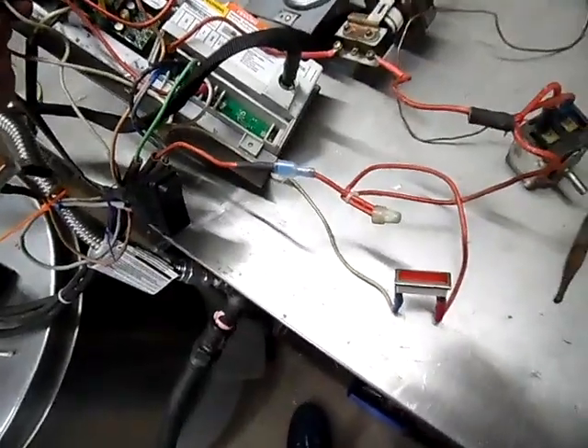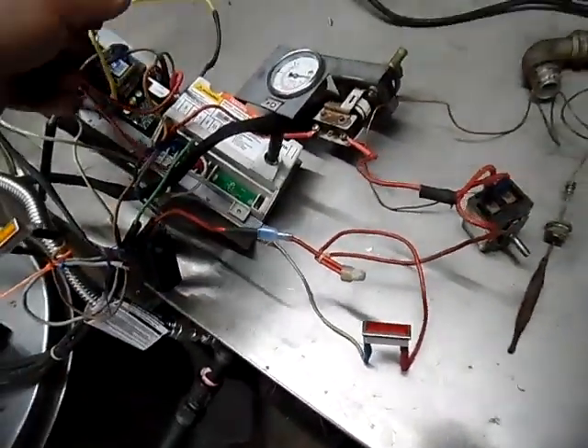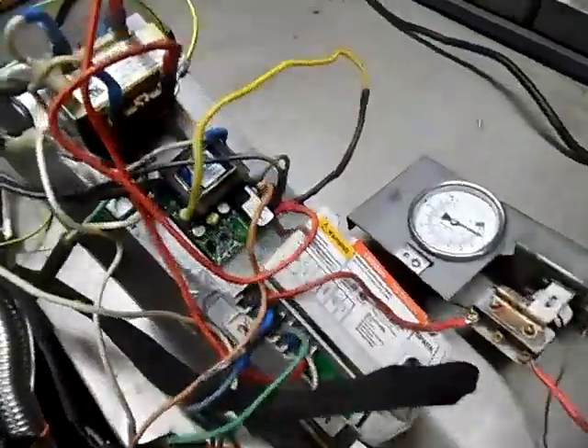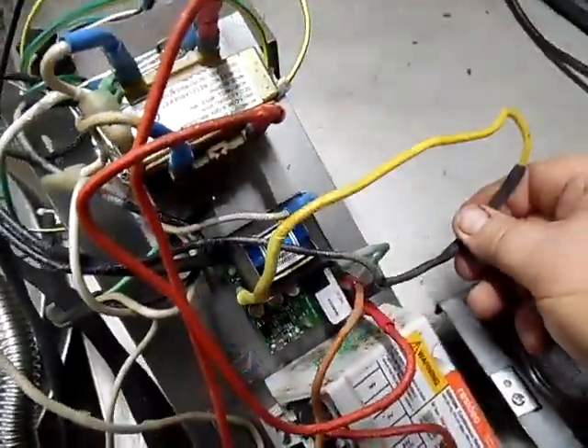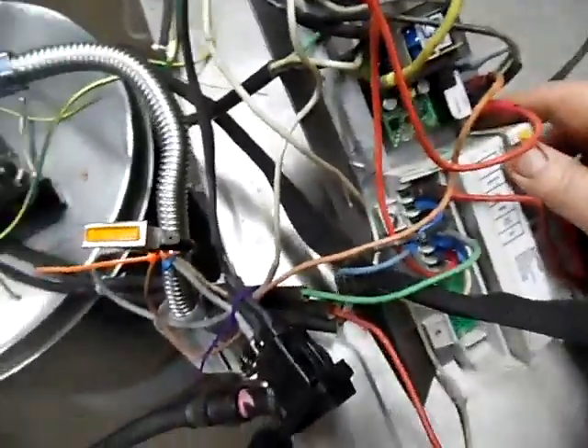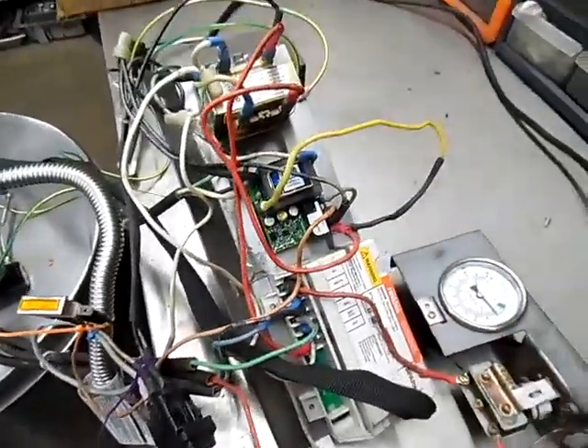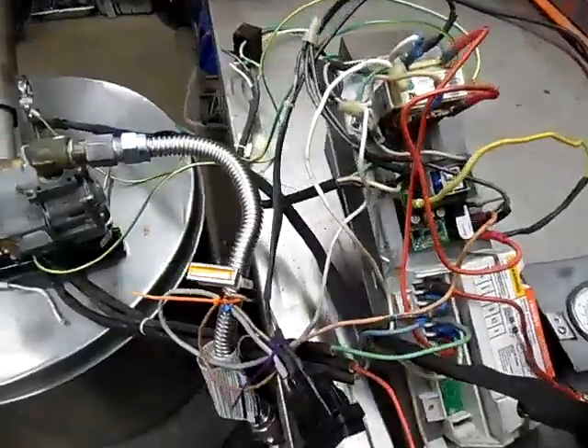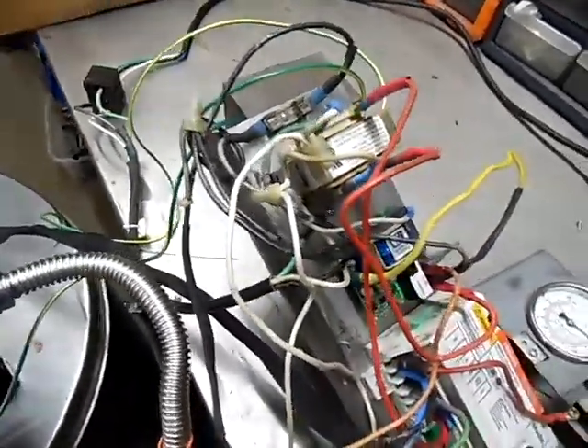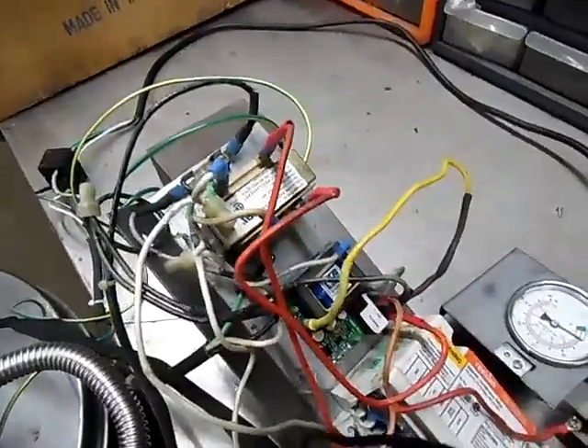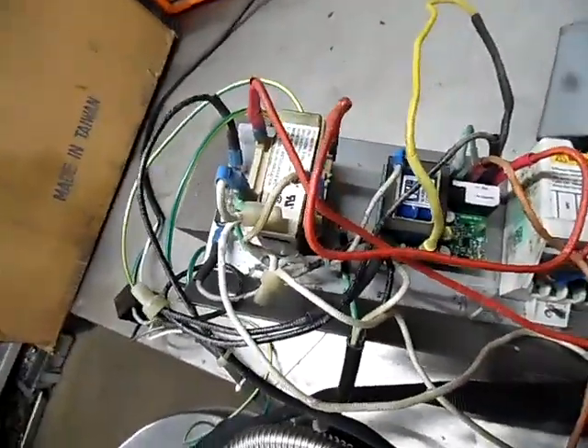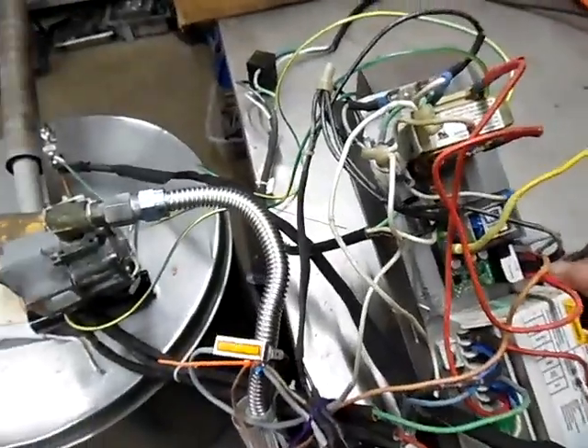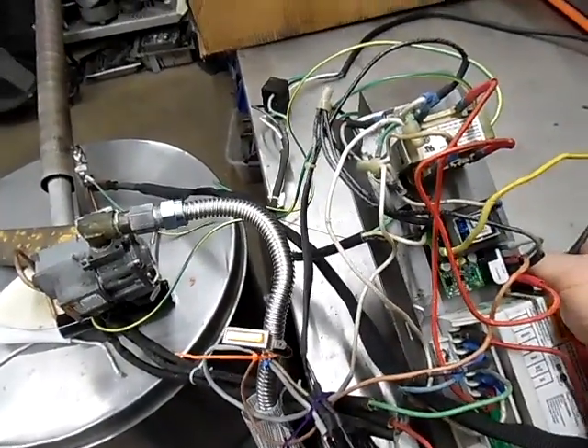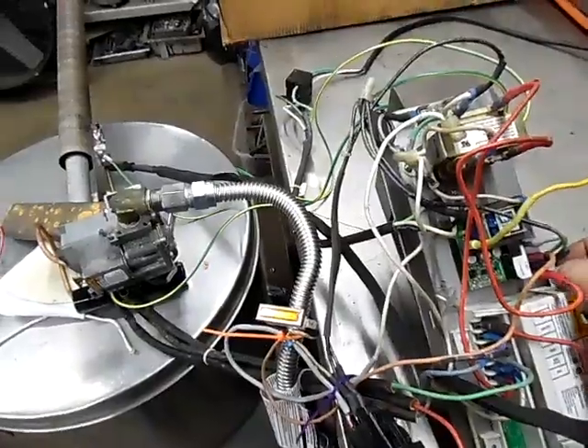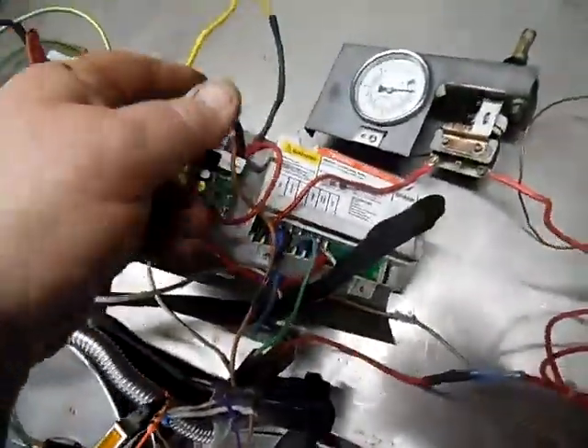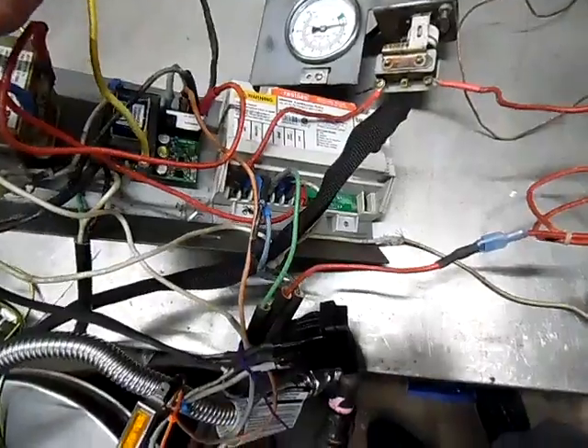The other thing is, when this first comes on, the first thing it does is test your water board. Right here, the yellow wire coming off the water board would normally go to the water probe. I have it grounded here. Okay, this is only for testing. Some people will take shortcuts when this acts up, and they'll take this water probe and ground it to the machine. The bad thing about doing that is now you're putting your machine at risk and yourselves, because you can have the pressures go crazy on this machine from overheating the bottom with no water in it. You can damage the welds. You just don't do that. If you've got something that's not working, replace it. This is simply for testing, and we're eliminating this outside of the kettle.